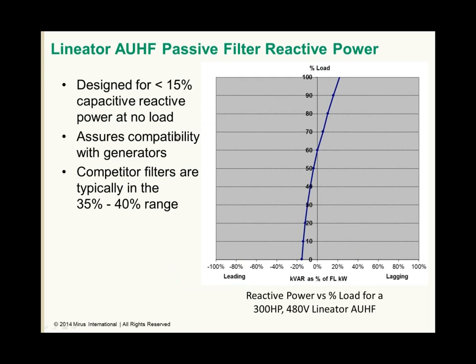As I mentioned, we design to have less than 15% capacitive reactance. This graph shown here is for a 300 horsepower, 480 volt filter, but is typical of all of the filters that we offer. Here we can see the leading reactive power in kVAR as a percent of the full load kilowatts. On the left side is leading power factor, and on the right side we have lagging power factor.